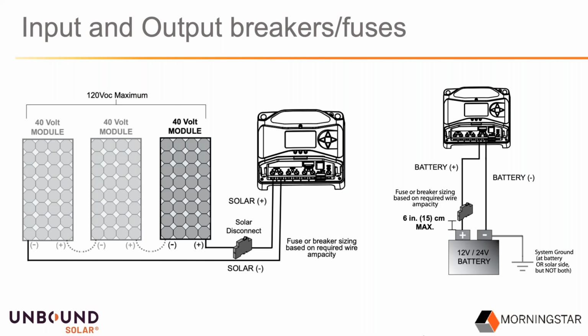On the right, it's showing the battery breaker or battery fuse. Typically the manual will tell you what size breaker or fuse to use here. If it doesn't, I would take the controller continuous output, let's say that's a 40 amp ProStar, and multiply that by 1.25. So if that's a 40 amp ProStar controller, I'd multiply 40 amps times 1.25 and use a 50 amp output breaker. And again, you need to make sure that your wire would have to be rated for at least 50 amps in that case. So making sure that your breaker, your overcurrent protection is protecting the wire.